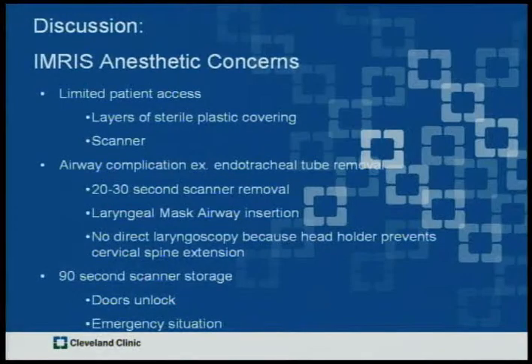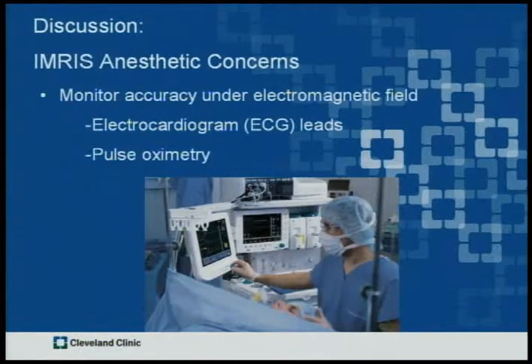It should be noted that in an emergency situation where a defibrillator is needed, it can be brought into the OR only after the MRI scanner leaves the surgical suite and is locked into the holding bay, a process that takes at least 90 seconds. Finally, electromagnetic interference with pulse oximetry and EKG tracing is a common occurrence.